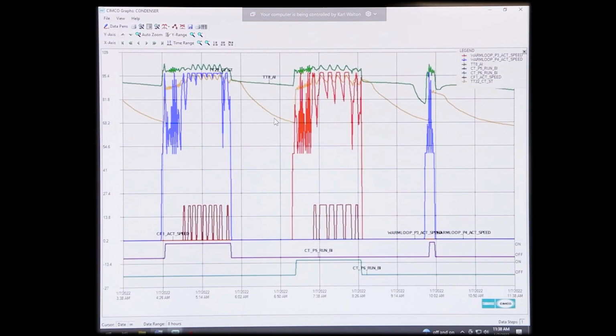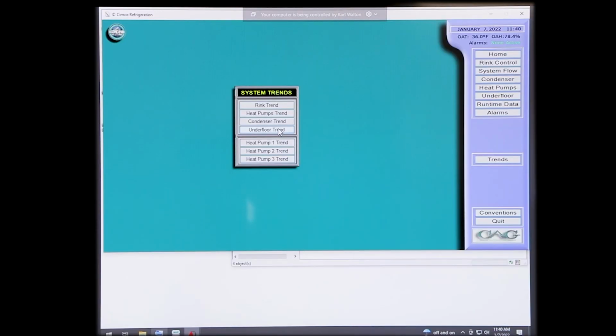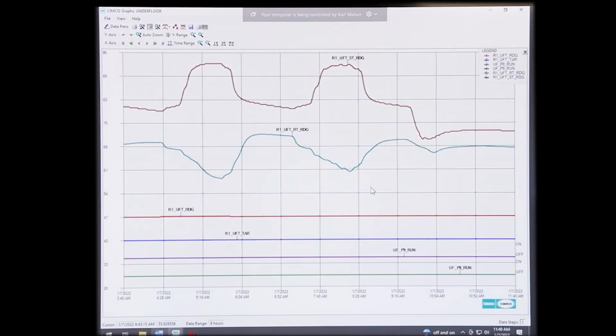Condenser trend is pretty much the same thing. Again, looking in the upper right corner, we're looking at different things. We're looking at the warm loop, P3, P4, actual speeds of the VFDs, TT8, analog input temperature. Cooling tower P5, P6, binary inputs. Again, looking at what we're running. Are we running P5? We're running P6. Okay? Looking at the actual starts and stops, actual speeds of the fan motors and different things. All right. Any questions? Okay, so next trend log is the underfloor.